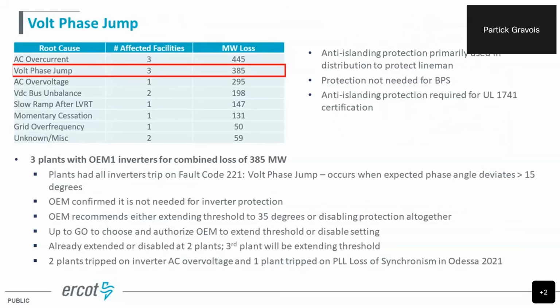So this is an anti-islanding protection, primarily used in distribution. It is not needed for the transmission level, but it is required for the UL 1741 certification. So that's why it gets shipped out with this protection in place. So this was 3 plants that had all the inverters trip on this fault code for 385 megawatts.